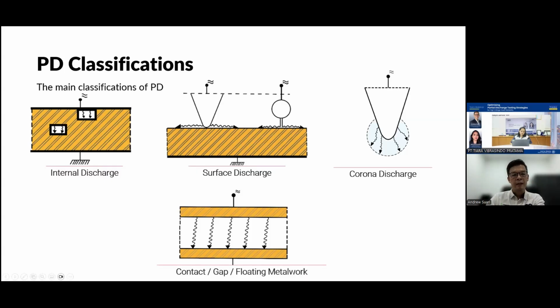Last but not least, we have gap contact floating metal. Sometimes if your contacts or surfaces are supposed to be tight, but were not tightened properly, there's a gap, and this will also cause a PD to happen. We call this the contact gap floating metal. So basically these four pictures sum up the types of PDs that we always see in our day-to-day work.